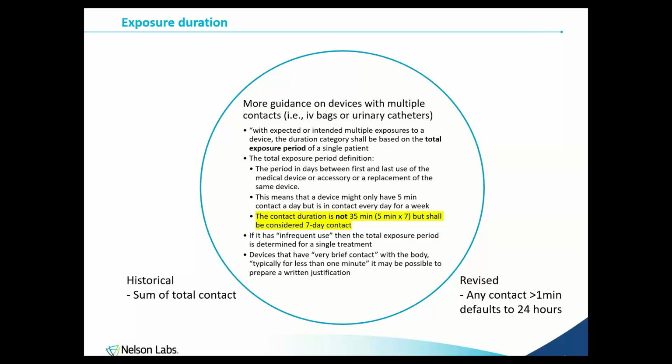because that's how we deal with things in toxicological concerns. So this is going to change a lot of devices' contact time, because like I said, in the past they've really just added up the time actually contacting the body and dealt with it that way. By the way, this was brought up by the FDA, so I'm pretty sure this is going to be recognized. This portion will be recognized by the FDA.